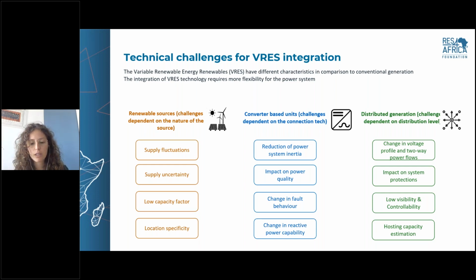We have challenges related to the type of technology. These technologies are connected to power converters because they are mainly DC sources, so it's a different type of technology. Instead of synchronous machines that were traditionally connected to the power system, we have power electronics that reduce the system inertia, that could have an impact on the power quality in terms, for example, of harmonics, that have a different fault behavior, so they don't inherently sustain, for example, the short circuit current. And they have different capability in terms of reactive power.